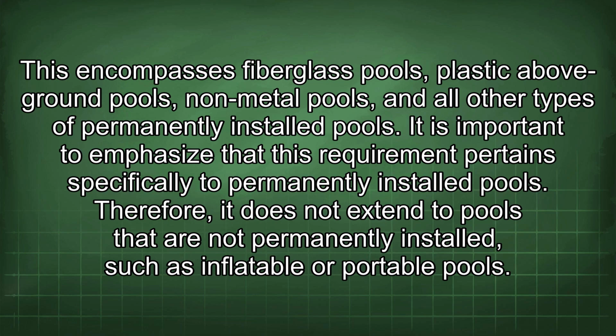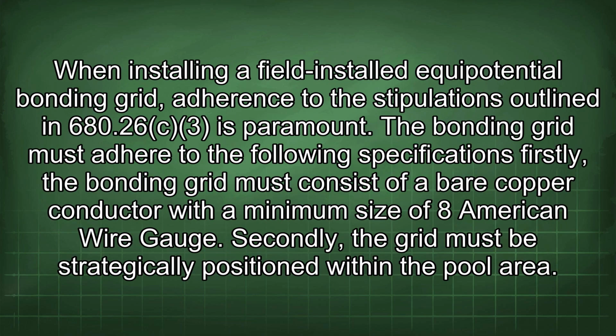It is important to emphasize that this requirement pertains specifically to permanently installed pools. Therefore, it does not extend to pools that are not permanently installed, such as inflatable or portable pools. When installing a field-installed equipotential bonding grid, adherence to the stipulations outlined in 680.26 is paramount. The bonding grid must adhere to the following specifications.